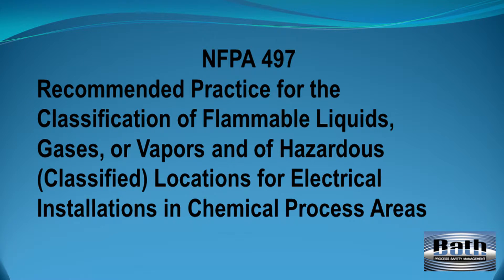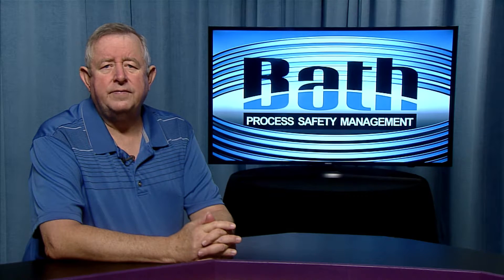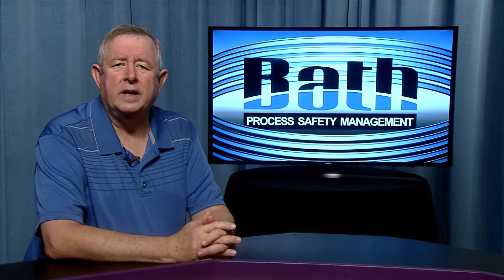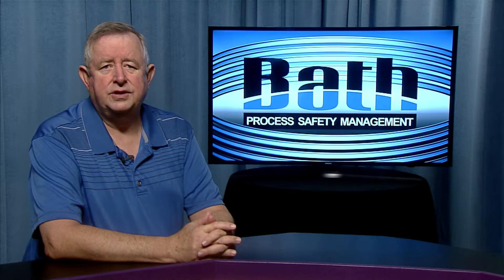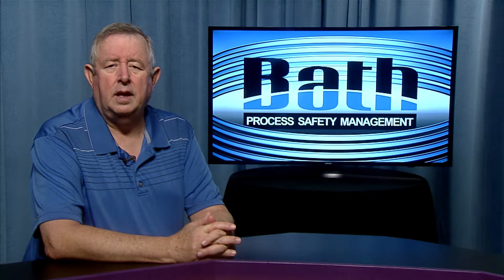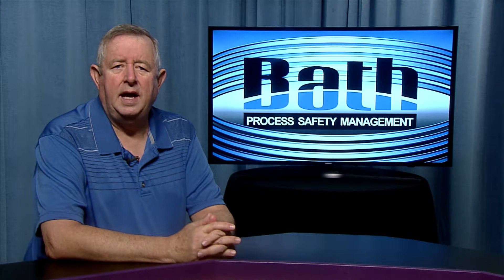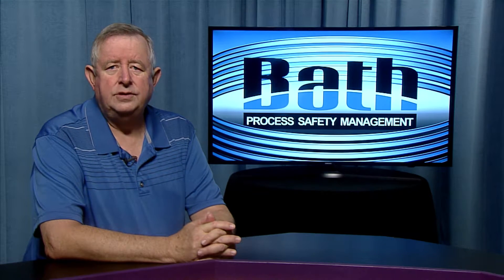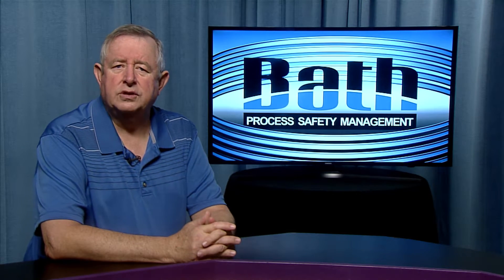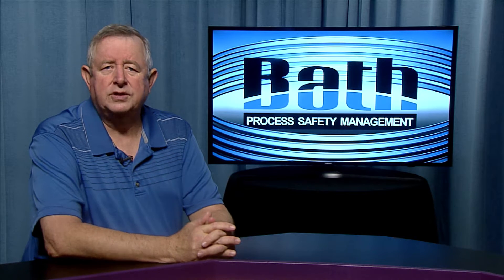The title of NFPA-497 is Recommended Practice for the Classification of Flammable Liquids, Gases or Vapors of Hazardous Classified Locations for Electrical Installations in Chemical Process Areas. Note that both of these documents cover Class I locations only, as defined by the National Electrical Code, NFPA 70, and do not cover those with combustible dust, which are Class II locations, or ignitable fibers and flyings that are Class III locations.